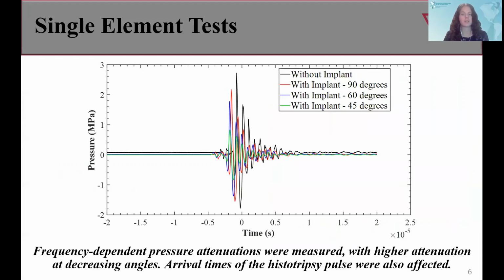Results from single-element testing revealed a frequency-dependent pressure attenuation with increased attenuation at increasing frequencies, matching previously published results when transducers are aligned perpendicularly to the implant. At decreasing angles, however, significantly higher attenuation was measured.